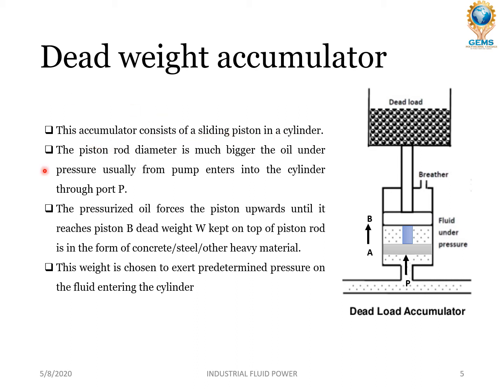The piston rod diameter is much bigger. The oil under pressure, usually from the pump, enters into the cylinder through port P. When there is more pressure coming in, this piston will move up. The pressurized oil forces the piston upwards until it reaches position B. The dead weight W kept on top of the piston rod is in the form of concrete, steel, or other heavy material.